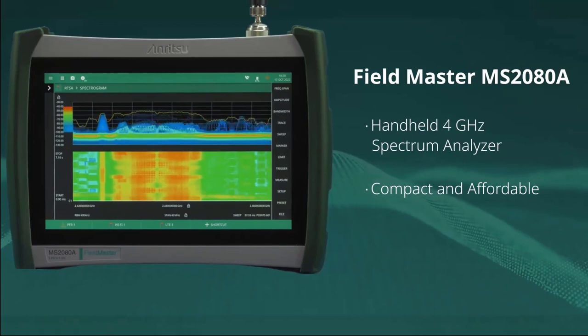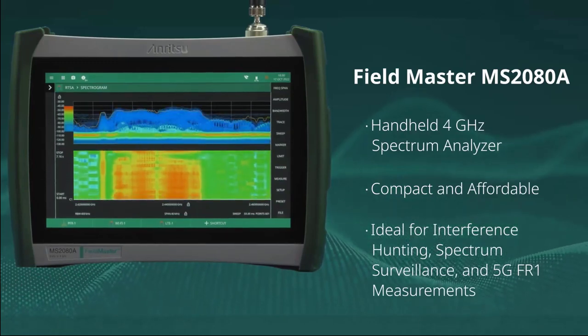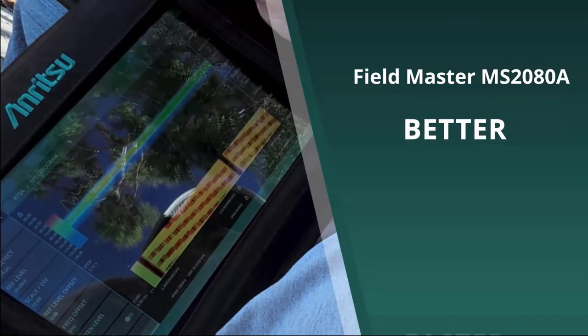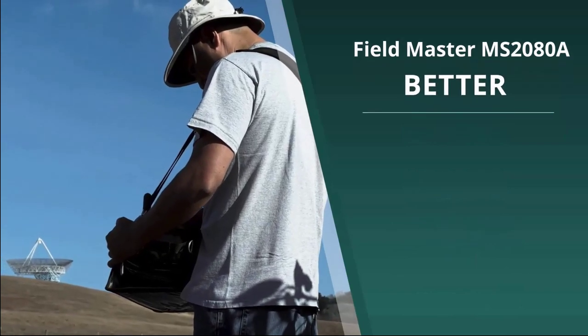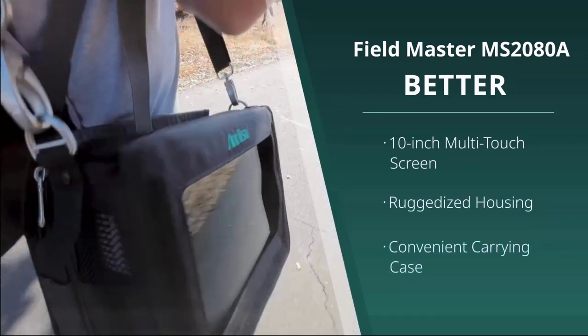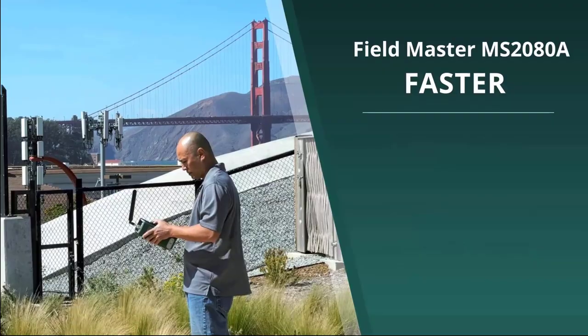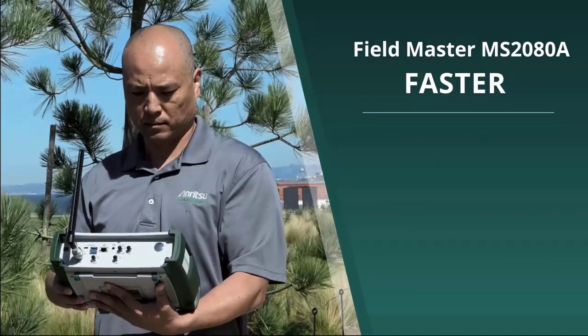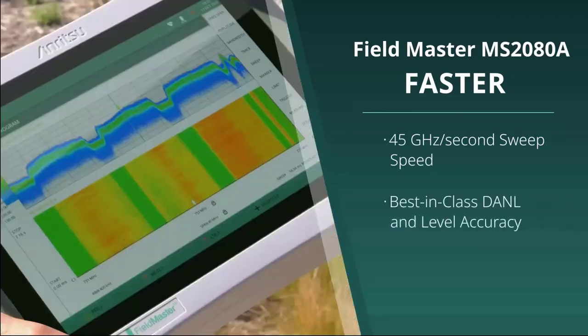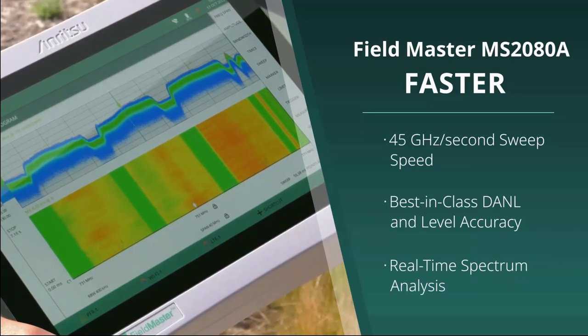The handheld 4 GHz spectrum analyzer incorporates all of Anritsu's expertise into a compact and affordable instrument that's ideal for interference hunting, spectrum surveillance, and 5G FR1 measurements. The Field Master MS2080A delivers on the Anritsu promise of being Better, Faster, and Smarter. Better: with its 10-inch multi-touch screen, ruggedized housing, and convenient carrying case, it is ideal for use in even the most challenging sites. Faster: with 45 GHz per second sweep speed to enhance interference hunting, best-in-class DANL and level accuracy for accurate transmitter measurements, and a real-time spectrum analyzer to find even the most elusive intermittent signals.